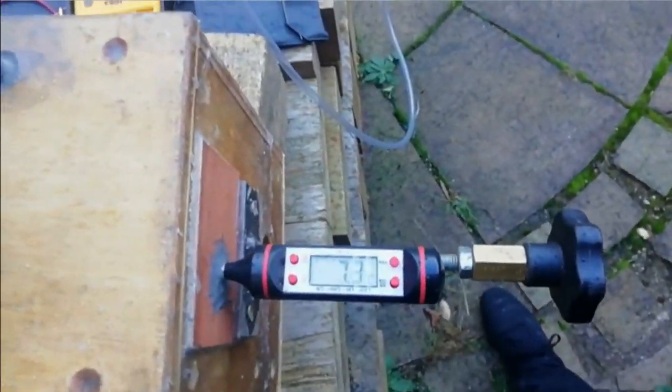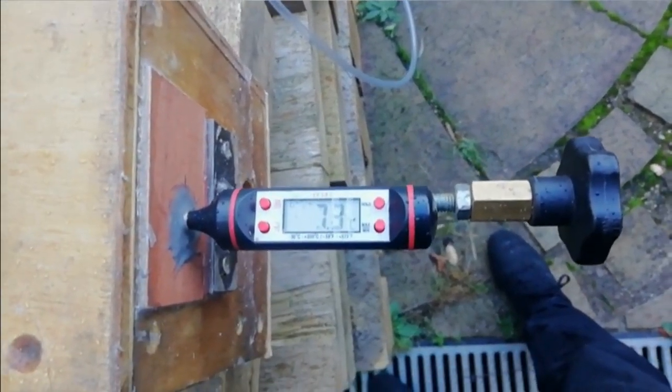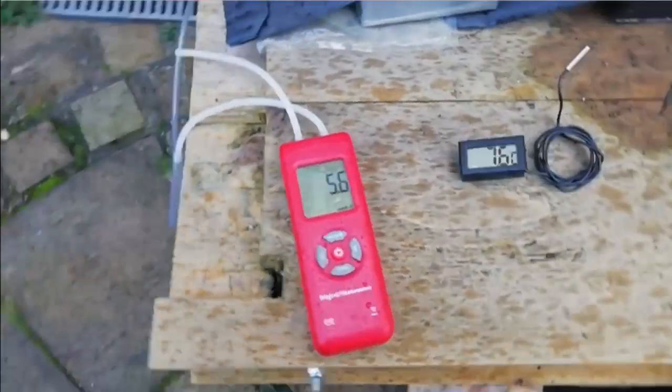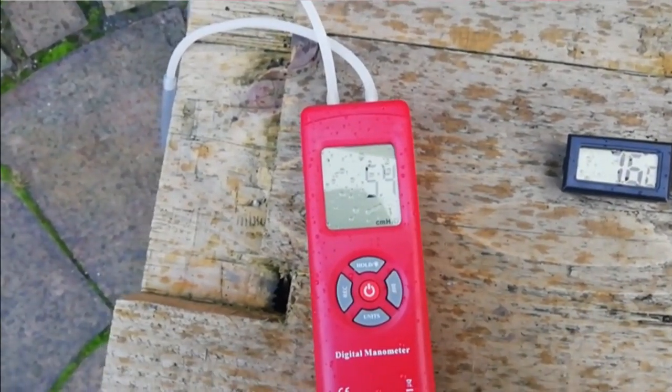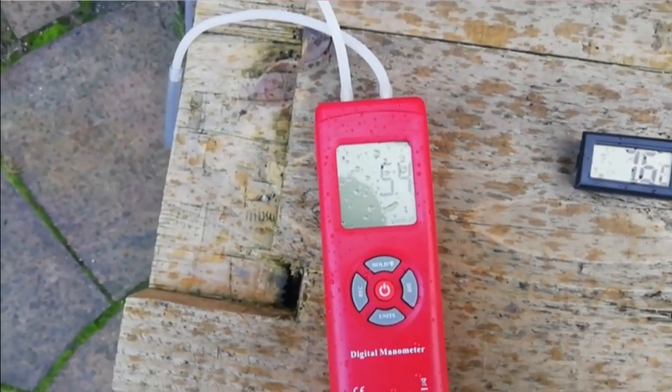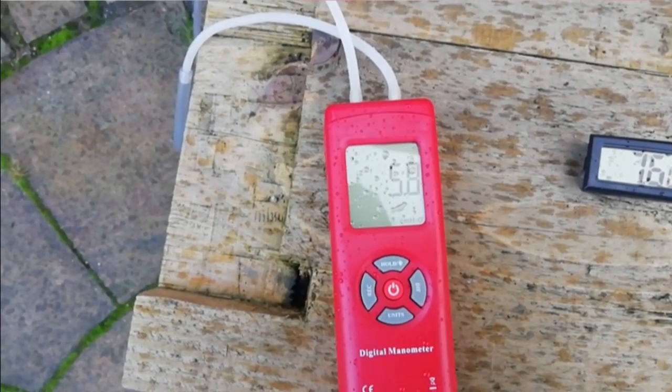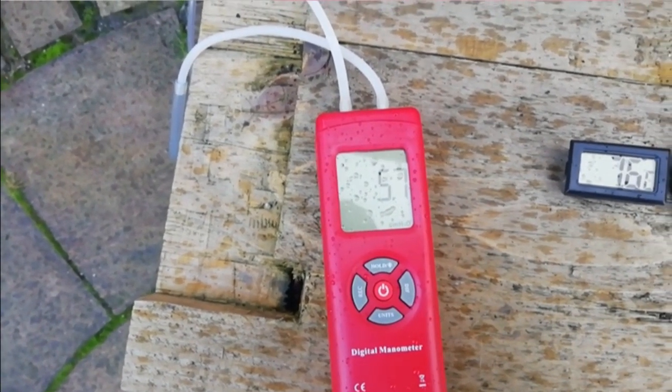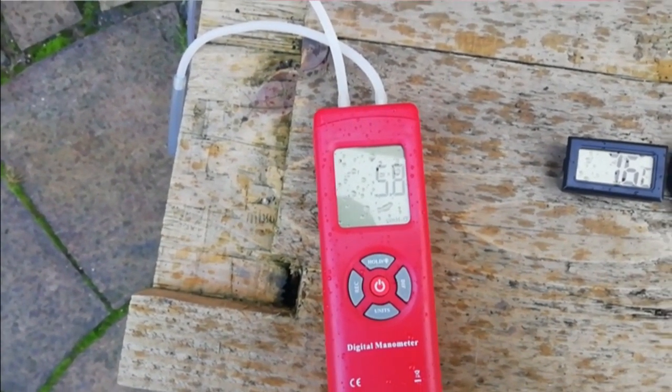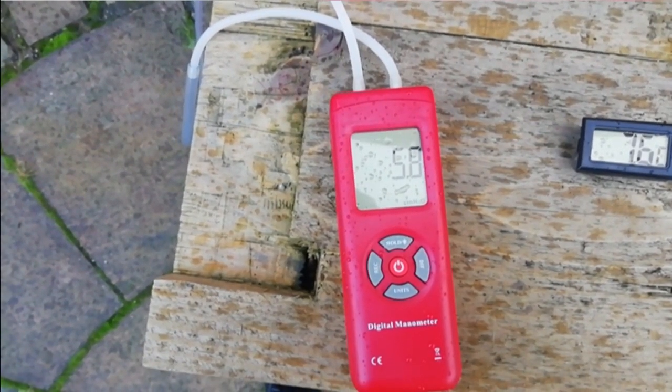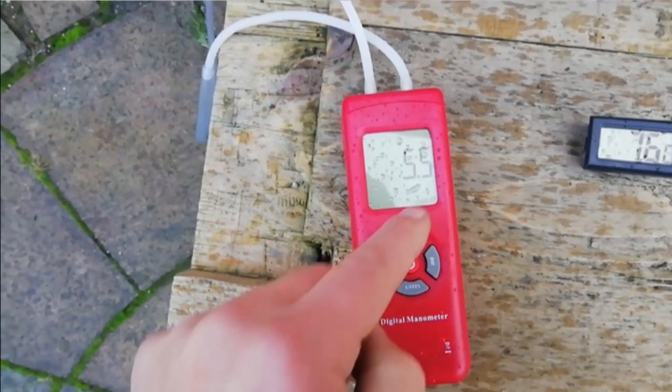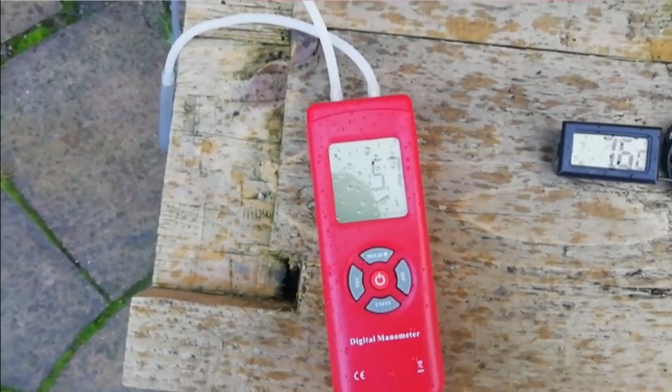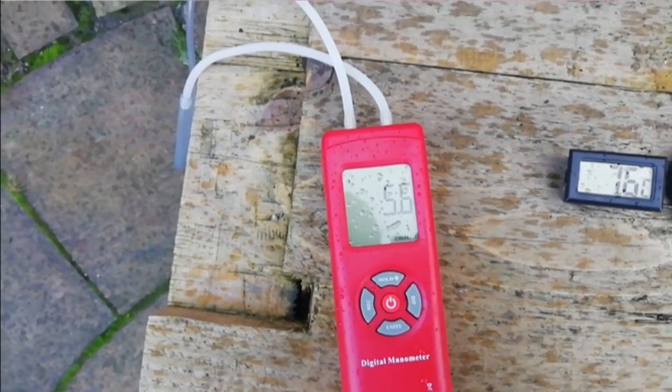Temperature inside the box, 7.3. Air pressure inside the box, air pressure differential, 5.4 or 54 millimeters of H2O. That's in centimeters but the actual measurement is in millimeters so it's 54, 55.